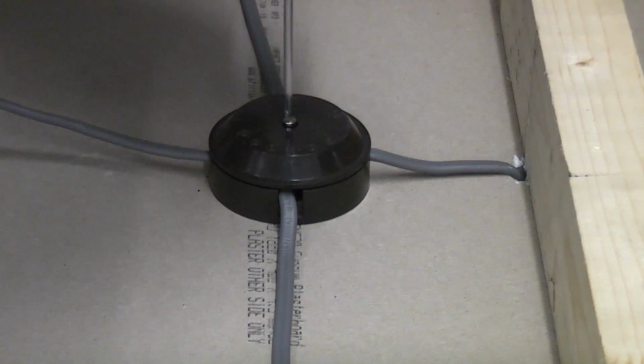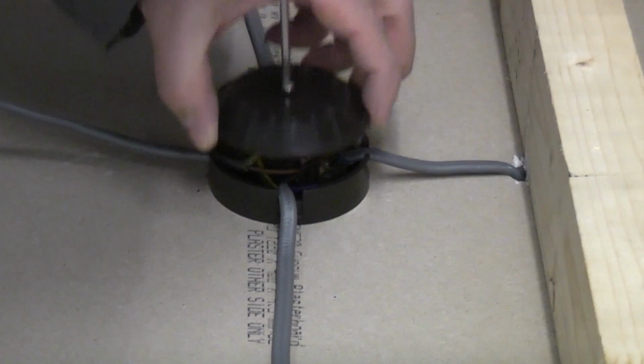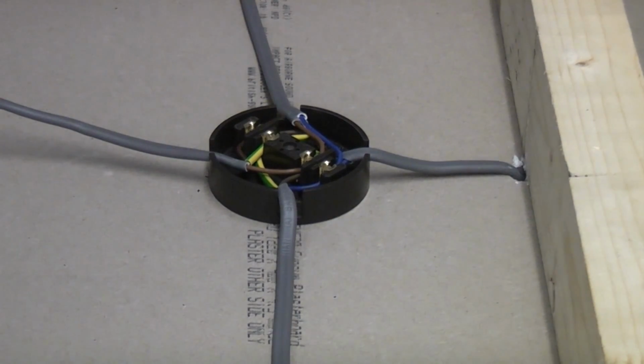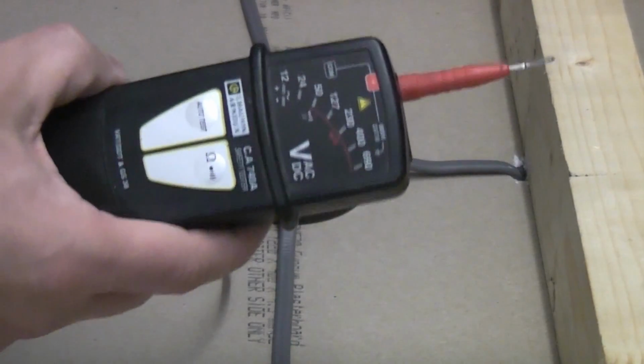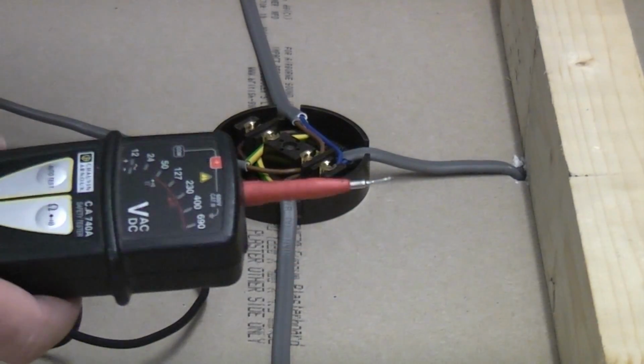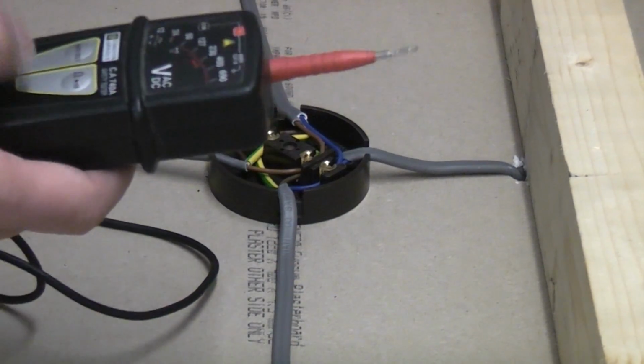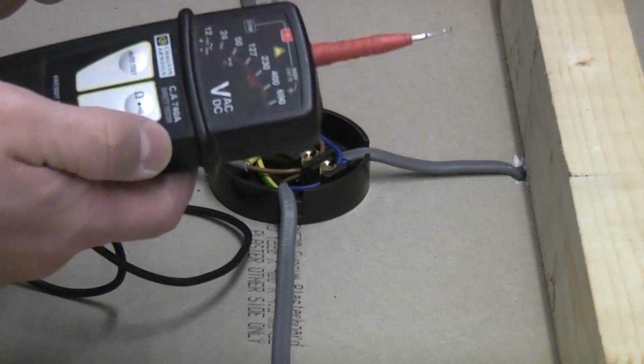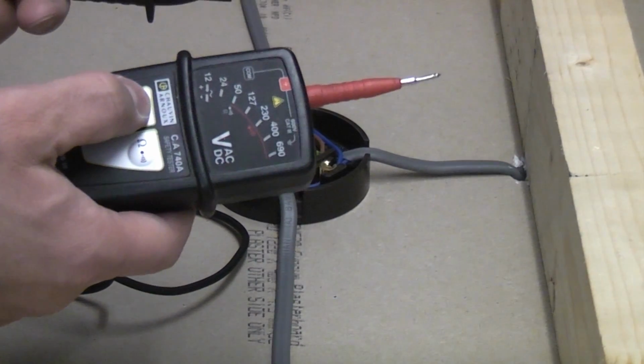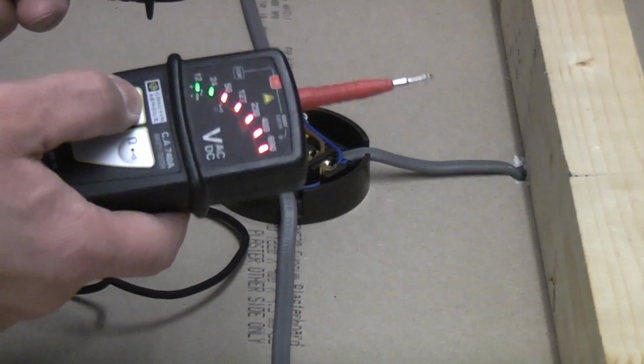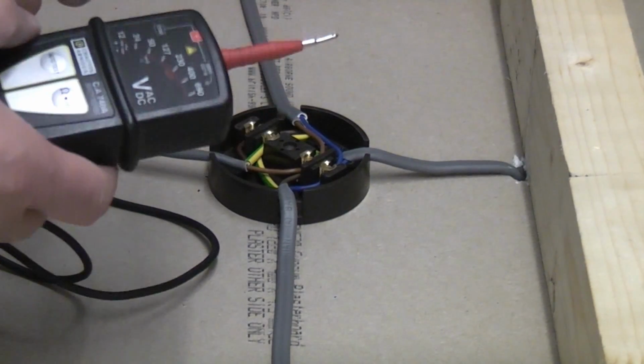Now we've locked off the electricity, we can remove the cover. And before touching any of the terminals, we can use the GS38 approved voltage tester to ensure that it is dead. Before you use this, you need to check that it's working by pressing the auto test function. If you don't have an auto test function, you will need a proving unit.